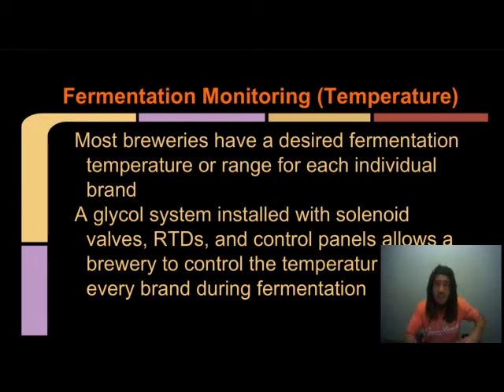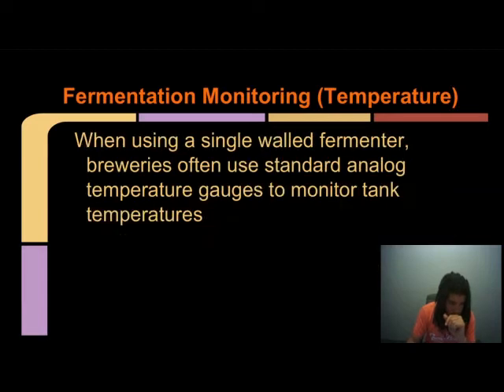I have an RTD, I have a control panel, I have solenoid valves, and I have a glycol system and jacketed fermenters. And that allows me to control all that. When using, however, a single-walled fermenter, breweries will often use standard analog temperature gauges to monitor the tank temperatures. So all you need is a quick analog deal. You don't probably need anything digital by any means for those.